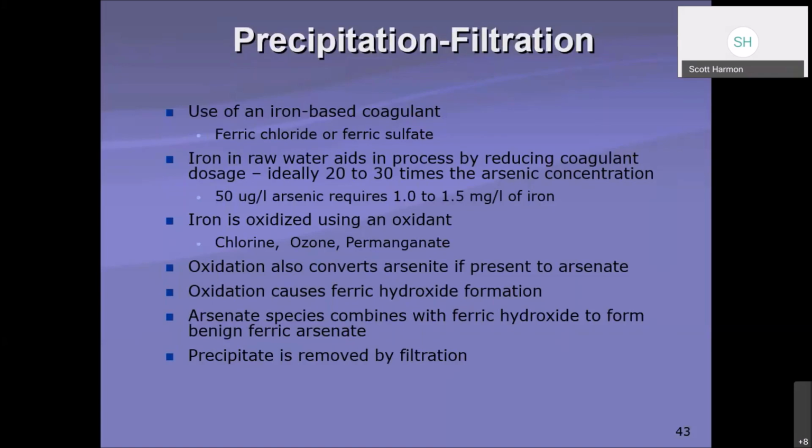Oxidation causes ferric hydroxide formation, which helps with floc, as we know. Arsenate species combines with ferric hydroxide to form a benign ferric arsenate. So this benign ferric arsenate can be precipitated or completely removed using a filtration process.